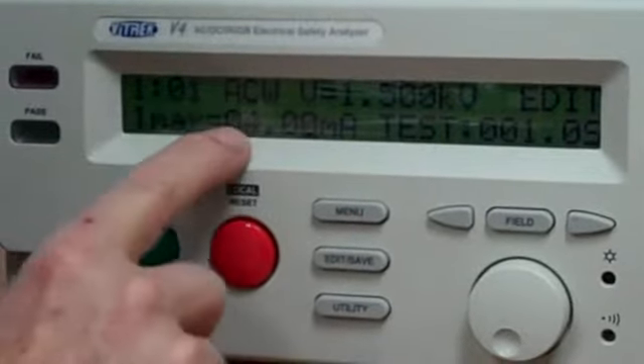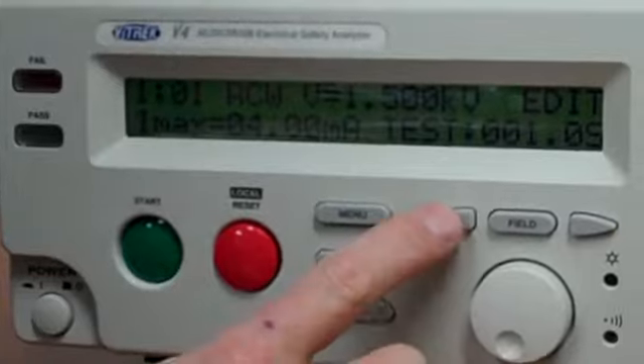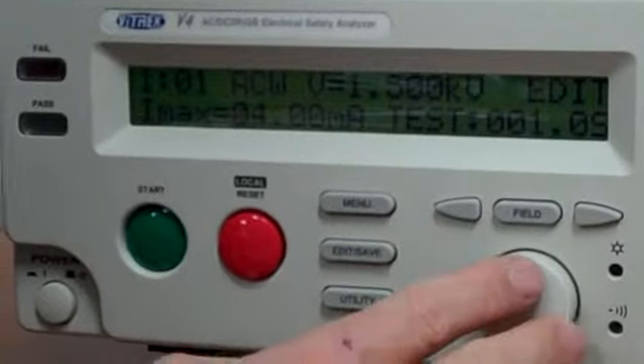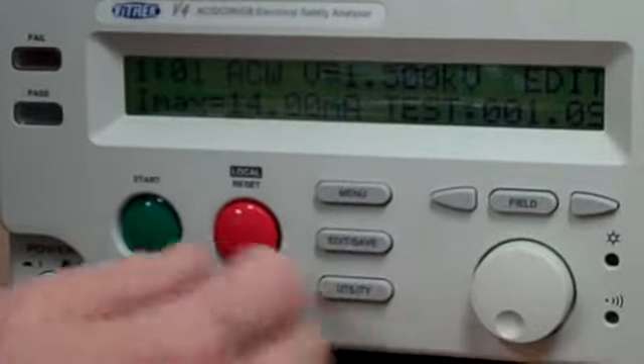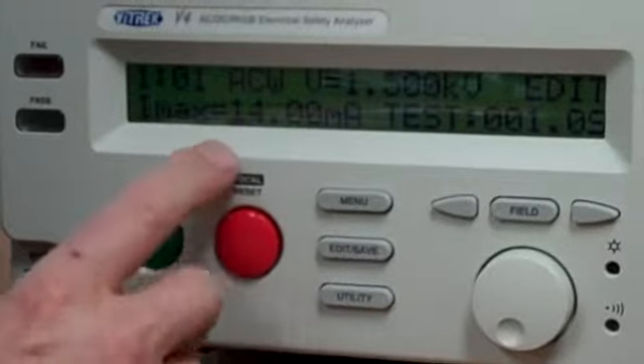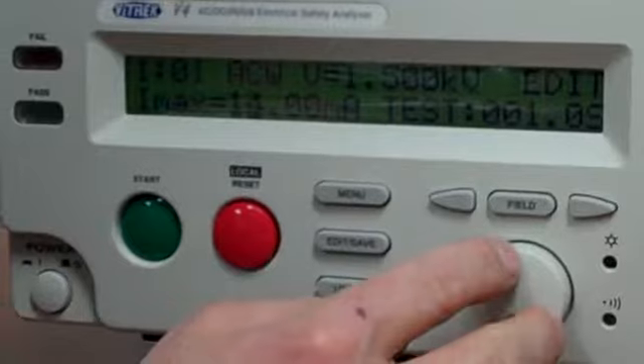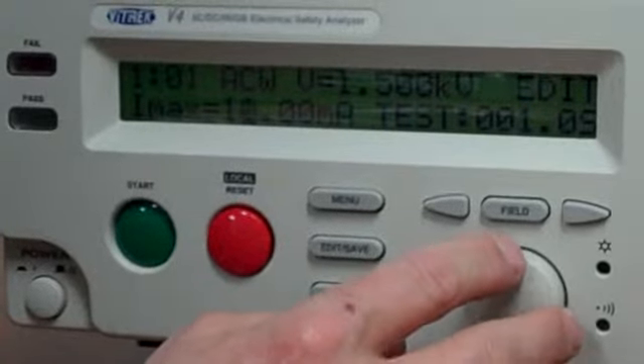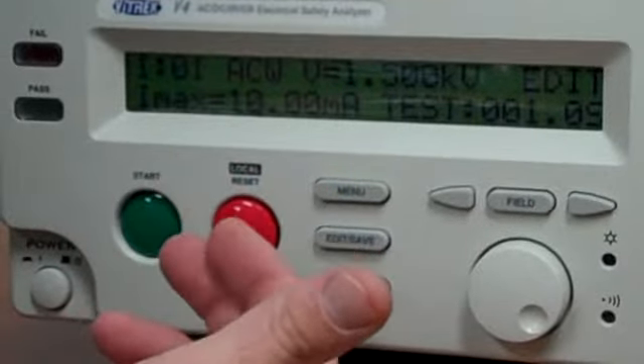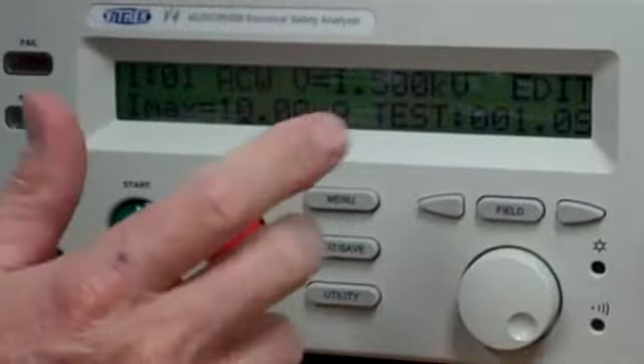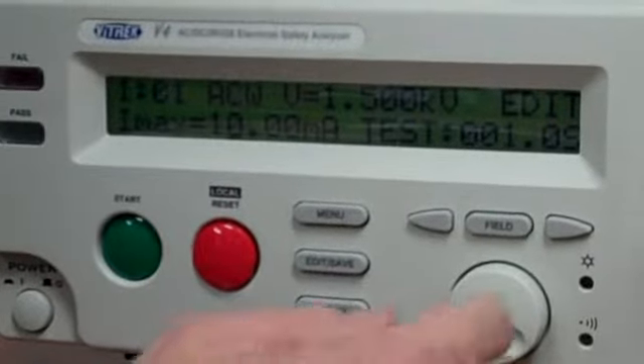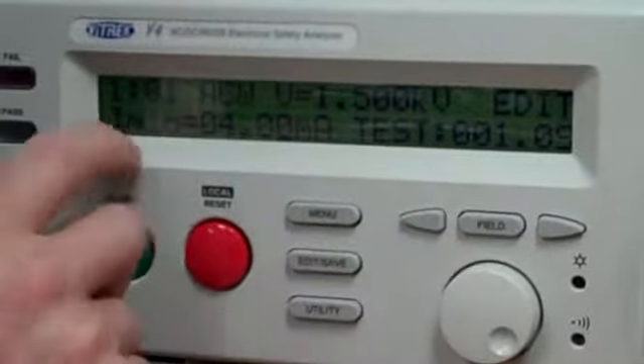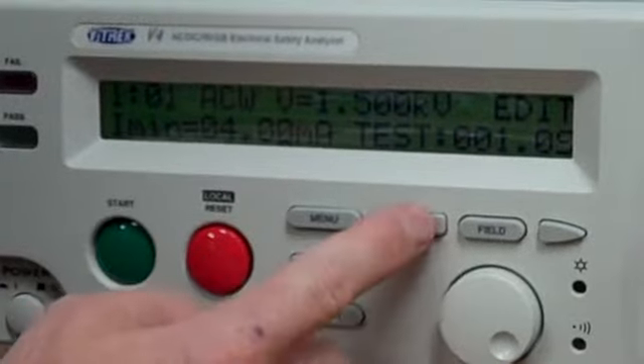The maximum current limit we have set here is 4 milliamps. I'm going to go up to 10 milliamps. That's a very popular current limit. This instrument is capable of sourcing up to 40 milliamps on AC. We'll set this down here at 10. Any current leakage that exceeds 10 milliamps will cause this unit to trip and indicate a failure for the device under test. The next field is the minimum current limit.